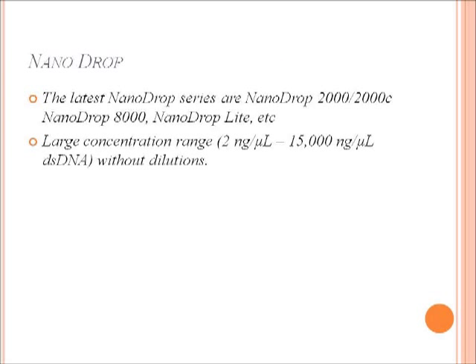Nanodrop is an instrument which can be used for assessing the purity and quantity of nucleic acid preparations. There are various different versions of Nanodrops available. The Nanodrop series includes Nanodrop 2000, 2000C, 8000, Nanodrop Light, etc. The advantage of using Nanodrop is that a large concentration range can be used for analysis, from 2 nanograms per microliter to 15,000 nanograms per microliter. Double-stranded DNA without dilution can be used for analysis using Nanodrop.